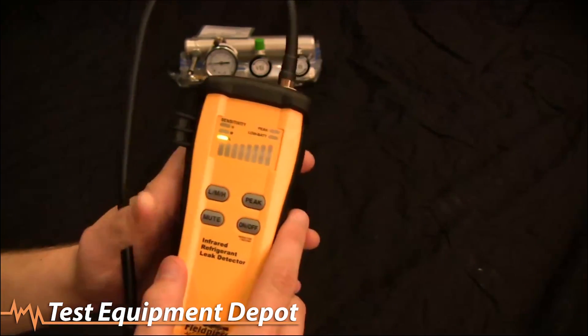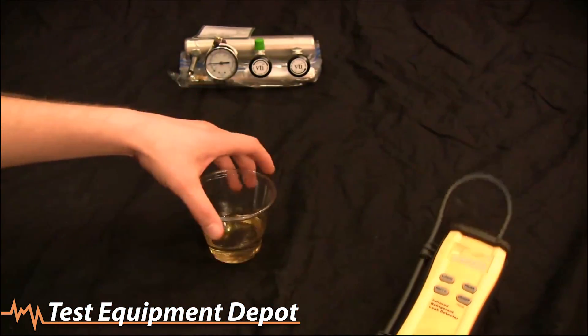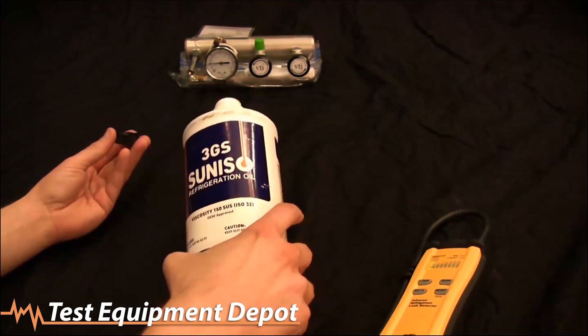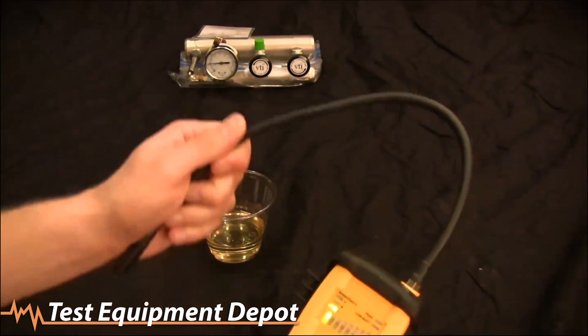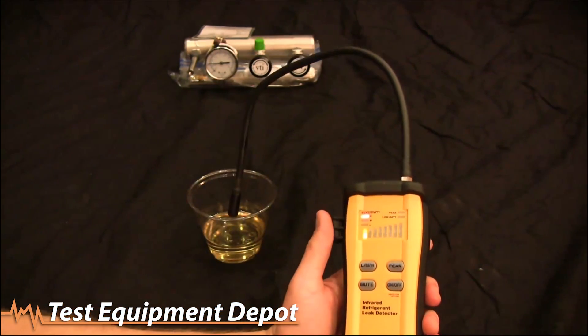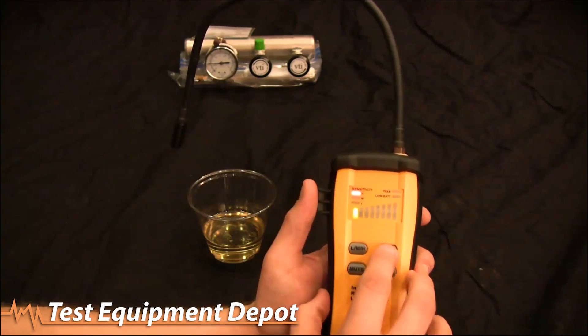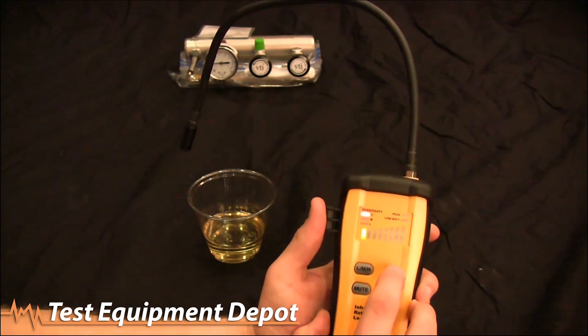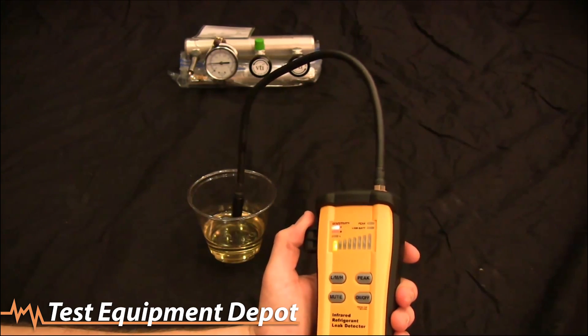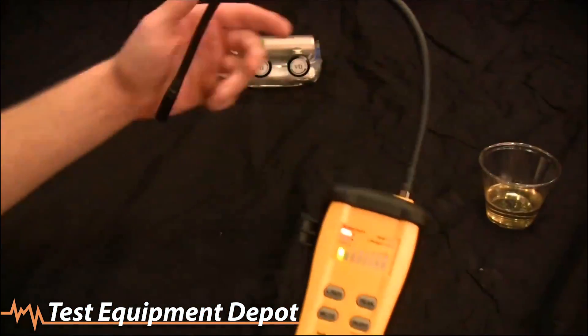What's also nice about infrared leak detectors is they don't go off on oil or moisture. I have some refrigerant oil here — I'll refresh it so we have fresh fumes. A lot of heated diodes will go off on refrigerant oil. Even on high sensitivity, and even in turbo mode with the LED fluttering, the SRL8 is not going to go off on refrigerant oil fumes. It will only go off on actual refrigerant, not refrigerant oil. And that's the SRL8.